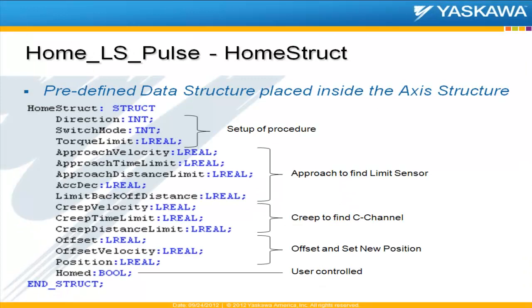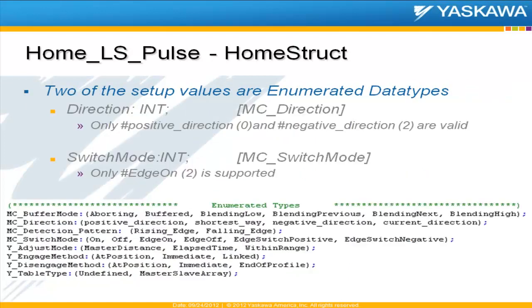A little more about the home structure. Inside the home struct — which is also placed inside the Axis Structure — you have things for setup, which is direction and switch mode. You have your approach configuration, your creep configuration, and your offset to new position configuration. There's also a bit in here for 'homed.' This is all user controlled, so the function block does nothing with it. It's for external use, typically on a power-up that requires homing — you'd initialize it to false, and then at the end of the procedure the user program would set it to true.